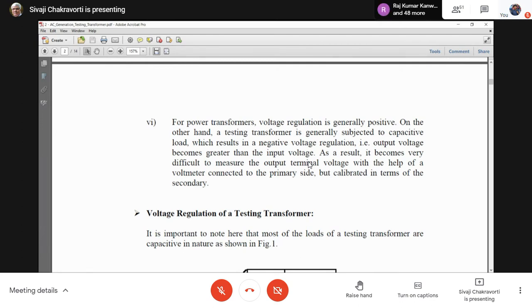Now, there are two things you have to keep in mind. Let me give you a practical example. Say somebody has come to the high voltage lab, and I am testing in our lab. As it is an 11 kV equipment, as per Indian standards, it has to be tested at 28 kV RMS. So the voltage that will be applied at the terminal of the equipment should be 28 kV RMS.